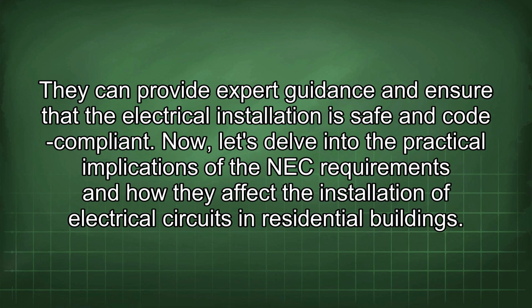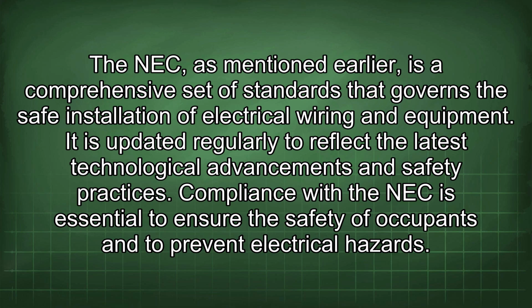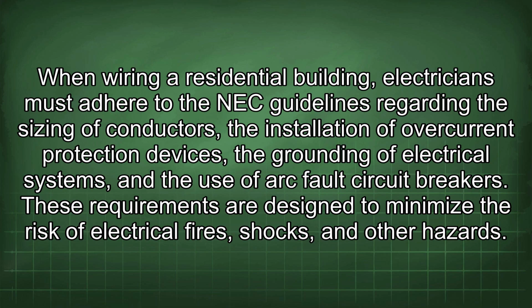Now, let's delve into the practical implications of the NEC requirements and how they affect the installation of electrical circuits in residential buildings. The NEC, as mentioned earlier, is a comprehensive set of standards that governs the safe installation of electrical wiring and equipment. It is updated regularly to reflect the latest technological advancements and safety practices. Compliance with the NEC is essential to ensure the safety of occupants and to prevent electrical hazards. When wiring a residential building, electricians must adhere to the NEC guidelines regarding the sizing of conductors, the installation of overcurrent protection devices, the grounding of electrical systems, and the use of arc fault circuit breakers. These requirements are designed to minimize the risk of electrical fires, shocks, and other hazards.